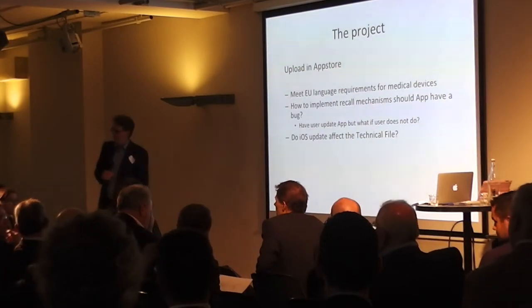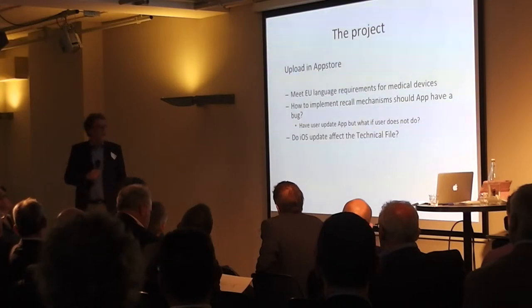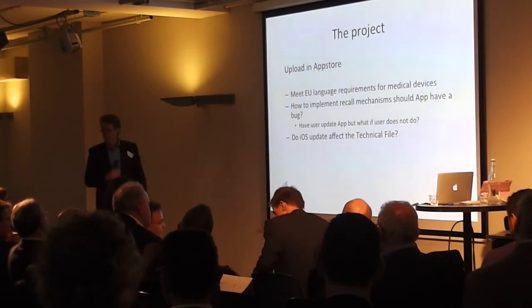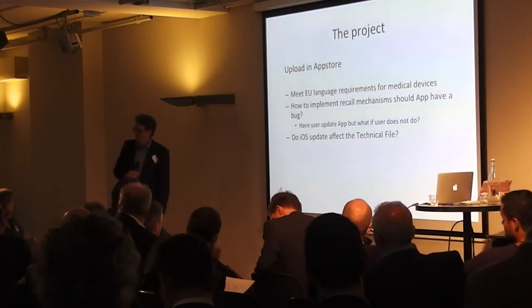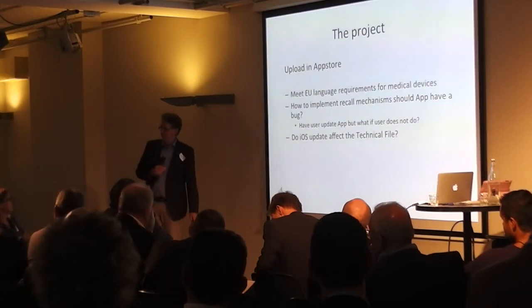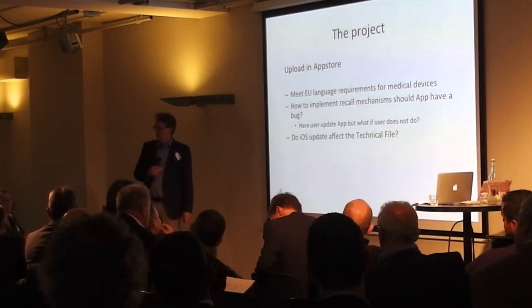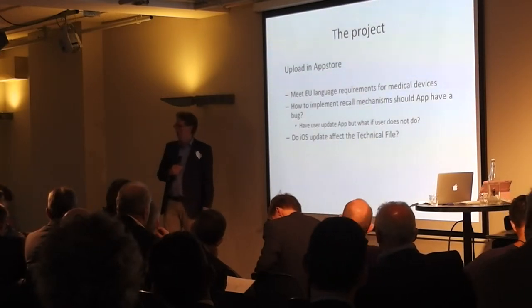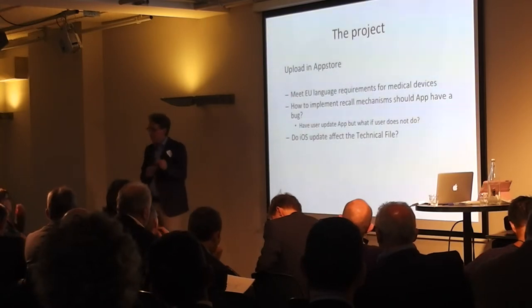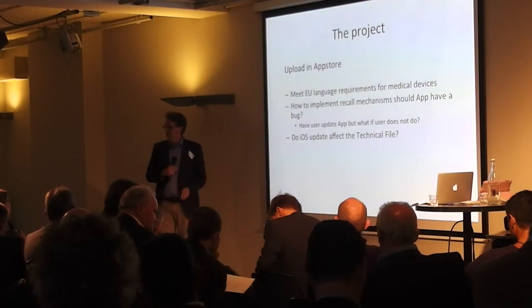If you upload a new update for your app, do you need to get another approval? If it has a minor update, which you see all the time on your phone, you need to go through the approval procedure again? You have a proper quality system in place, etc., but still. Well, it depends. No, basically no. But you would need to anticipate by describing in your procedures that the minor revisions can be implemented, which have no clinical relevance, and set criteria for that, that you can implement them.